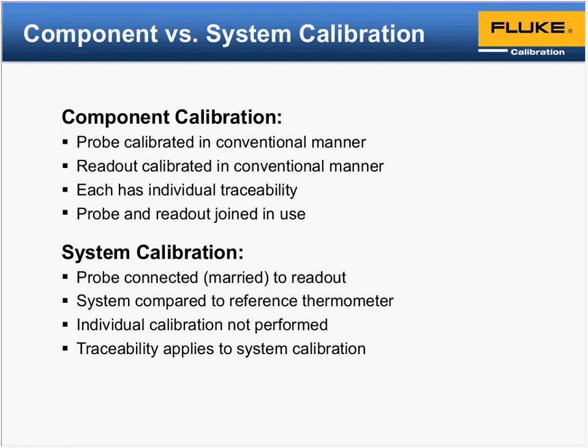Next question is, can a Drywell be calibrated, and how would you do that? Yes, Drywells can be calibrated, and if we're saying the Drywell is traceable, it would have to be calibrated. The calibration method would almost refer to that slide we went through where we had the unit in the heat source. The only difference is the Drywell would become the unit under test.